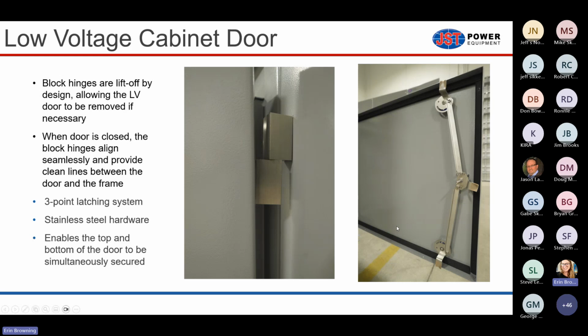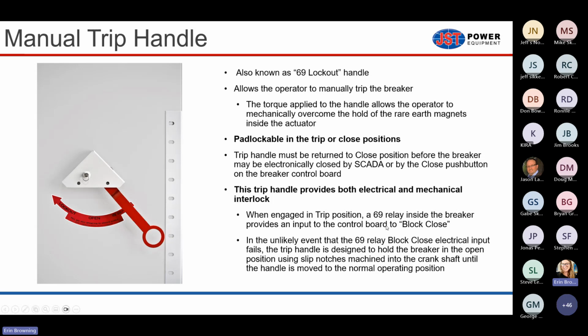And then there's a manual trip handle for locking out the breaker in the open position. This is known as the 69 lockout handle. It's padlockable. You move it to the open position, and then you move it a little bit further to the left to lock it out. And then to move it back into the open position, you have to pull a pin lock.